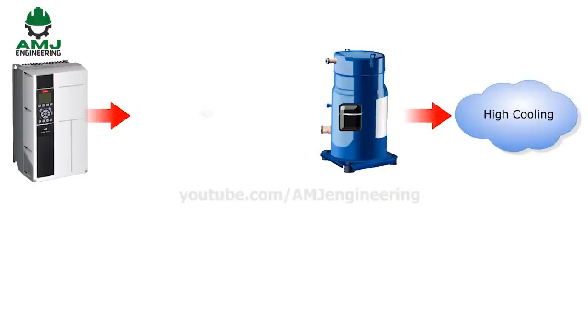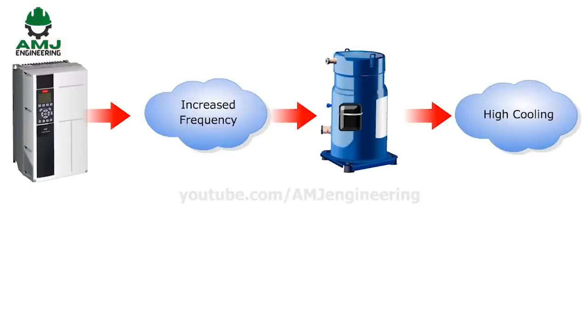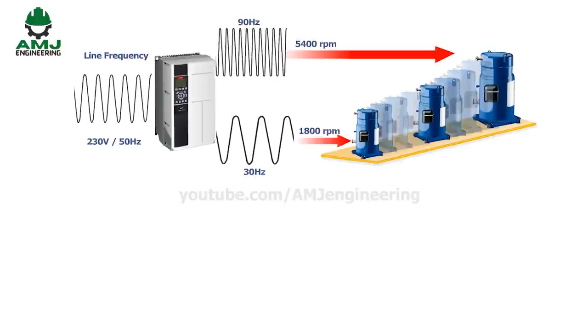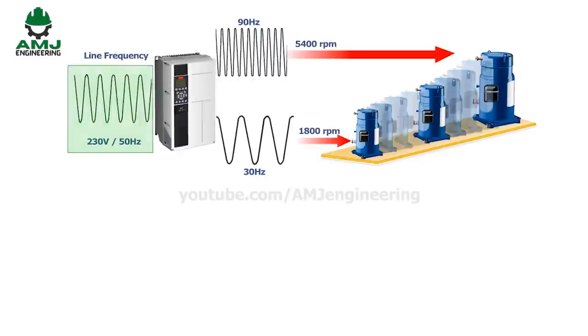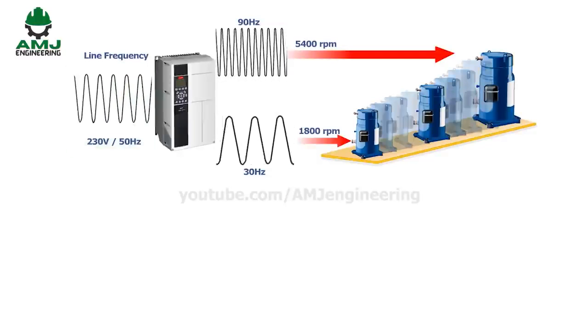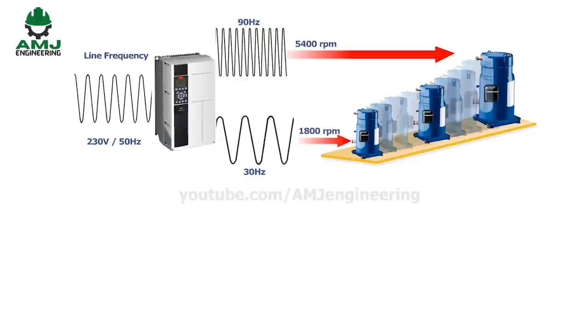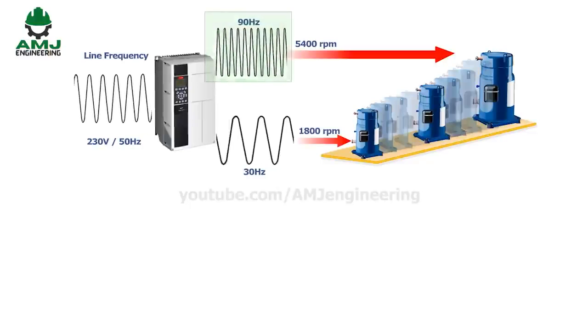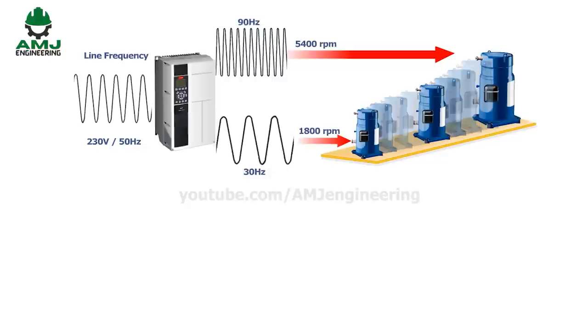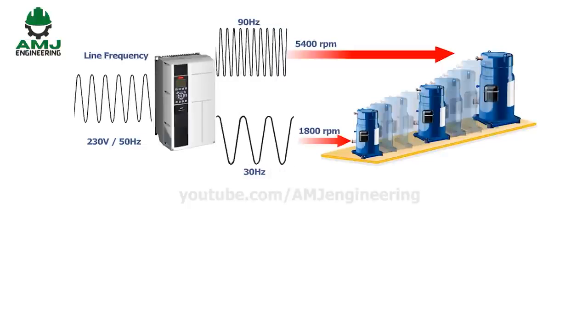For periods of high cooling demand, the input frequency of the compressor is increased. For periods of lower cooling demand, a lower input frequency is supplied to the compressor. Periods of normal cooling demand use the standard 50 or 60 Hz frequencies. Maximum required cooling capacity is achieved using 90 Hz for scroll compressor speed. On the other hand, minimum required cooling capacity is achieved using 30 Hz for scroll compressor speed.